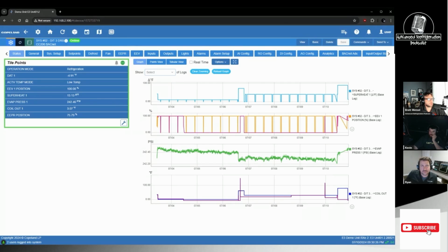Just so, for a case controller, the benefits, being the obvious ones, is multi-evaporators. Instead of having a ton of main case controllers, you have one main and then the expansion modules. On the main, you can have either the control, a stepper or a pulse width. Stepper wired at the bottom, pulse width at the top left. It's the same model number, same part number. Out of the box, pick what valve you want. If you have 2 valves, you need an expansion. 3 valves, get another expansion.